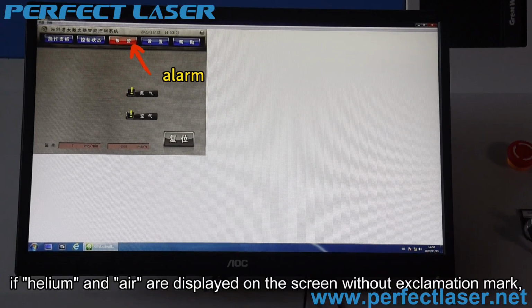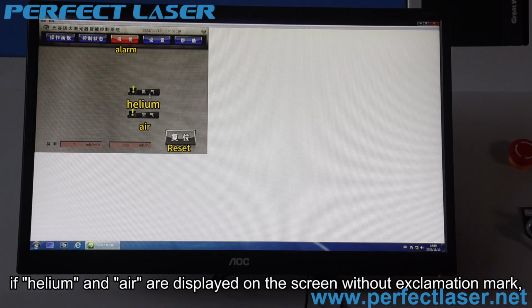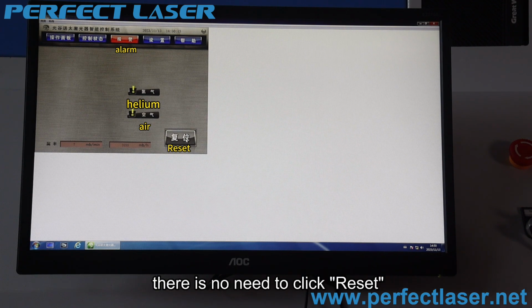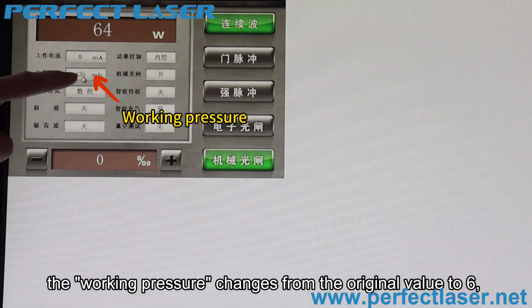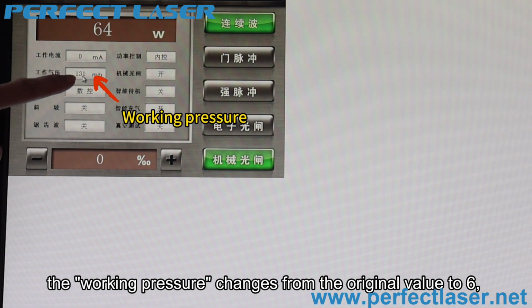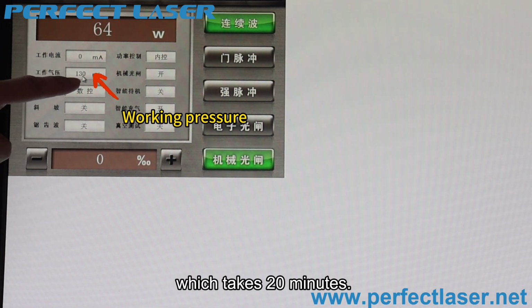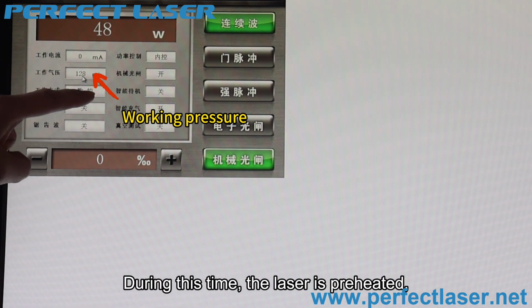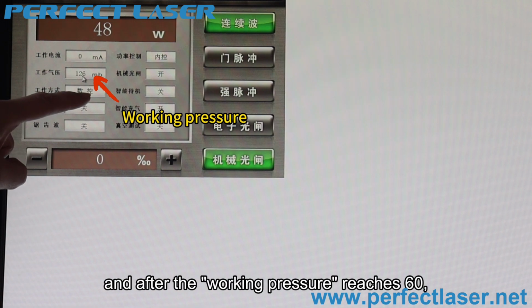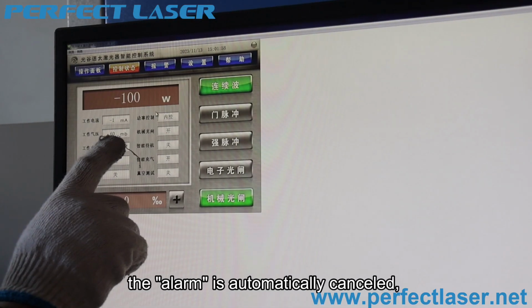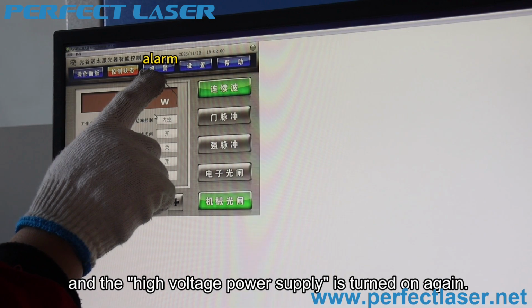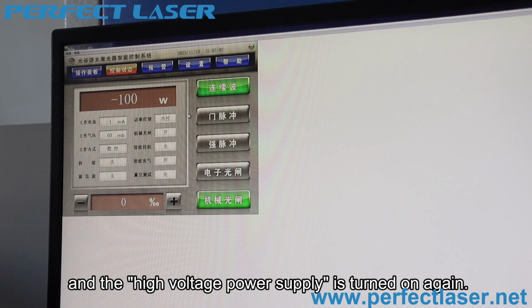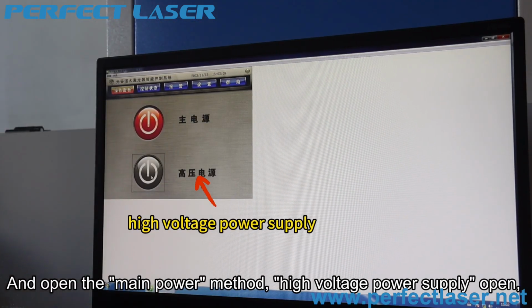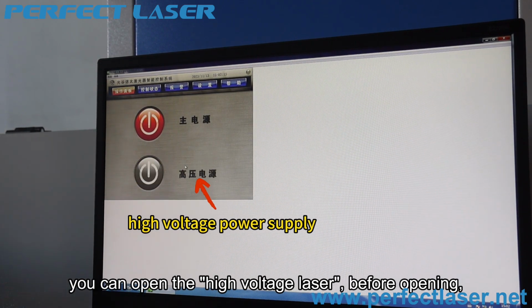Click alarm. If helium and air are displayed on the screen without exclamation mark, there is no need to click reset. The working pressure changes from the original value to 60, which takes 20 minutes. During this time, the laser is preheated, and after the working pressure reaches 60, the alarm is automatically cancelled, and the high voltage power supply is turned on again. And open the main power method, high voltage power supply open. You can open the high voltage laser.